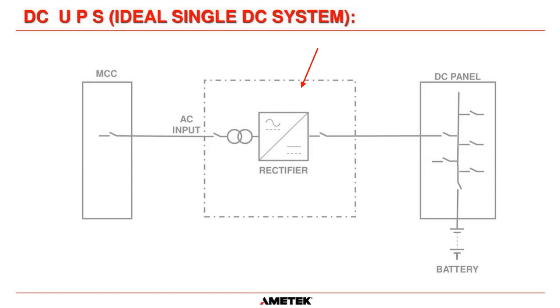Okay, so this is a relatively good system because if you needed to work on the charger itself, you could open this disconnect here. Your batteries would still be able to supply power to your load circuits here, and you could do some maintenance on the charger if possible. And in truth, if you have a spare breaker like I've shown here, you could temp in a secondary charger, a rental charger or a temporary battery charger into that breaker there while you're working on the other system. It gives you some flexibility for maintenance. So that is an ideal single DC system.